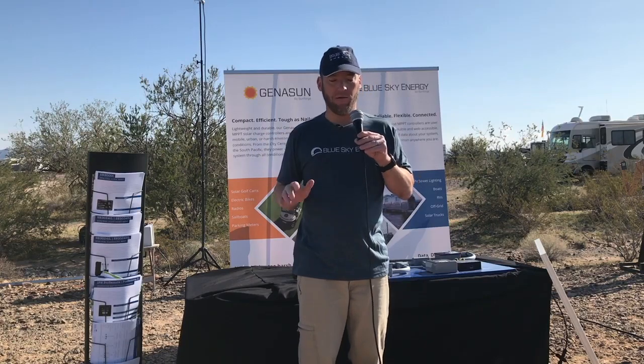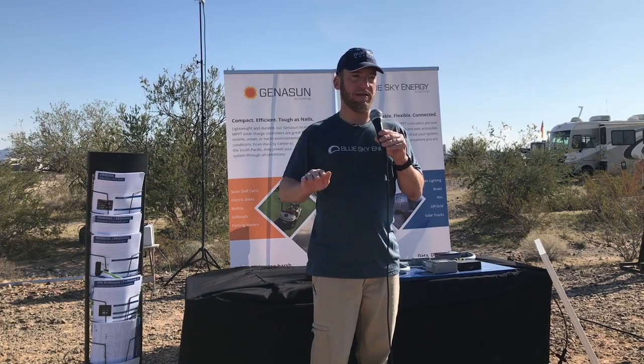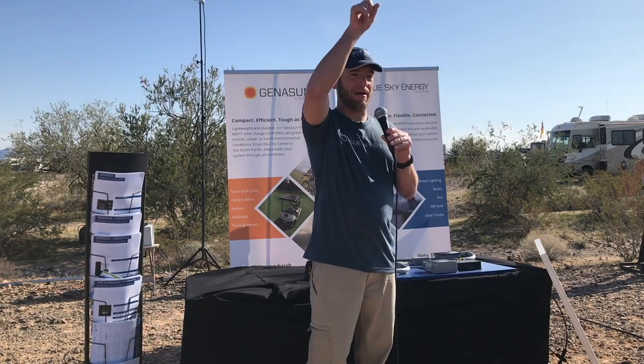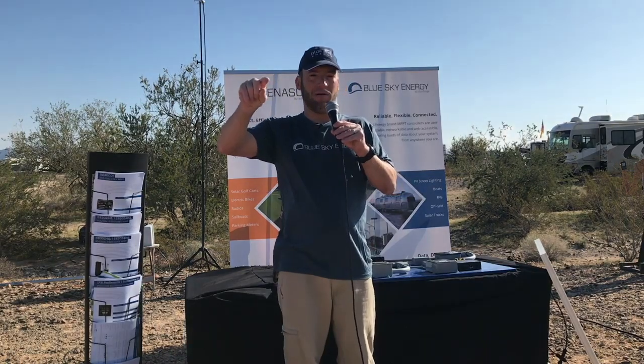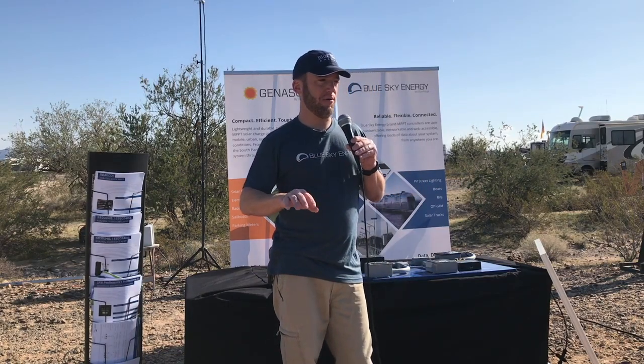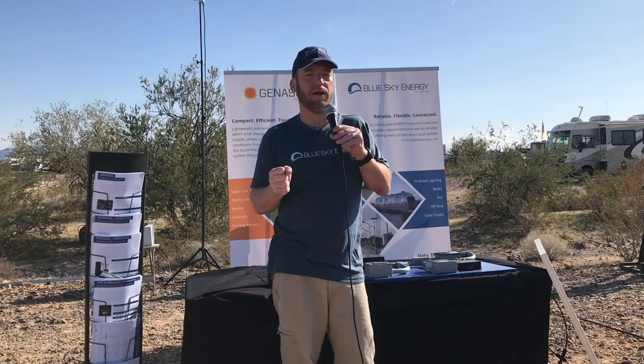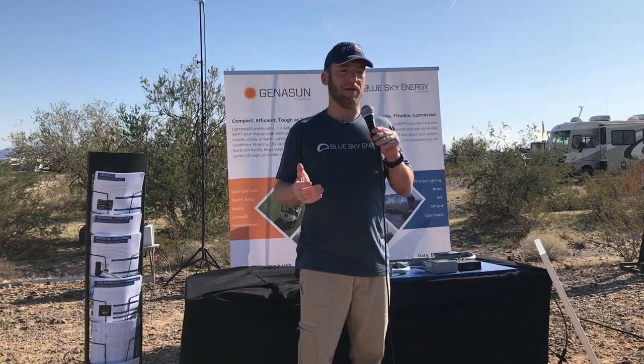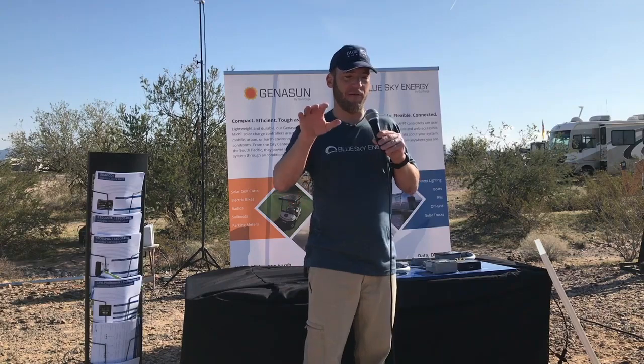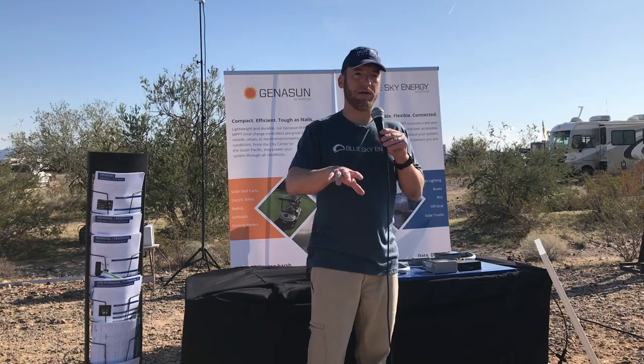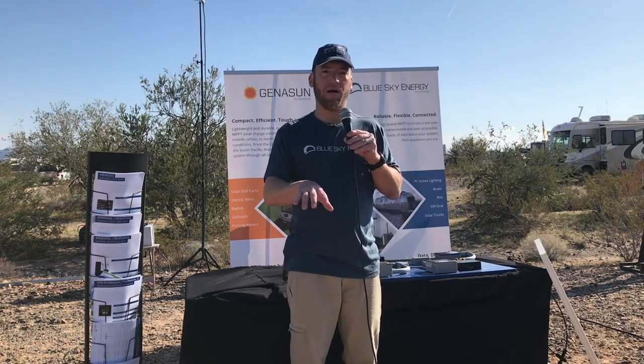The other thing a lithium battery management system has to do is make sure your lithium battery doesn't get discharged below a certain point. If you look at the discharge curve on a lithium battery, it's like a hockey stick, really stable, and then it just falls off the map. With a lithium cell, if you discharge it below a certain point, you need to charge it really slowly or else it explodes. So what a BMS does is cut off your battery from any loads, preventing your cells from getting to that low voltage where it would be dangerous to charge them at a high rate.